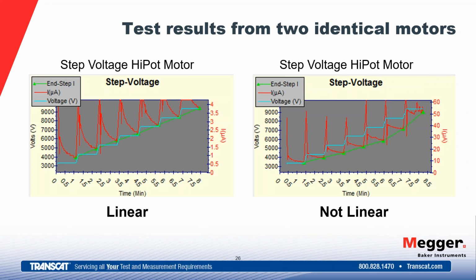This test passed. It didn't trip. Our minimum megohm values are still high, but it failed the nonlinear test. It's telling us that as we raise voltage up on this, at some point our insulation is becoming weaker. The other indication here is that at this final step we do have instability in our current. So I would propose that the very next step would actually trip the tester at that point.